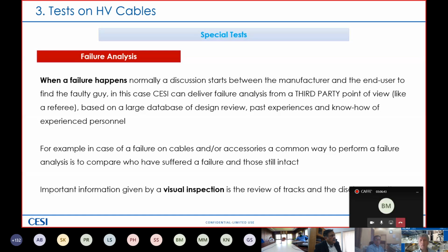For example, a common way to perform a failure analysis of a cable or accessories is to compare the sample that has suffered a failure with a sample that is still without any failure. Of course, we need all the manufacturer specification in order to verify if the mounting of the cable termination or of the cable joint was done properly. An important piece of information is given again by the visual inspection and a review of all the tracks and all the operations performed.